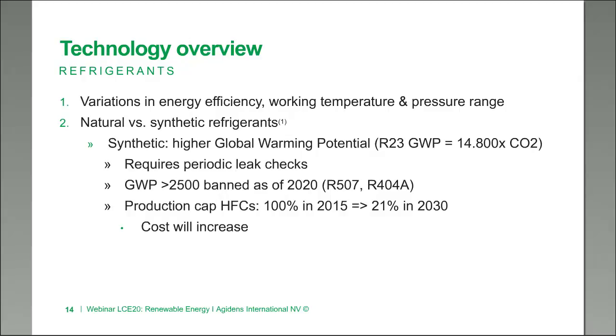All gases with a global warming potential above 2,500 have been banned as of 2020 — we're thinking about R507 and R404A for instance. Even the ones not yet banned — all those containing HFCs — will see significant production caps over the coming years. 2015 has been set as the baseline, and production will be reduced by 79% to just 21% of 2015 levels by 2030. That clearly means that HFC-containing gases will become more and more expensive as supply diminishes.